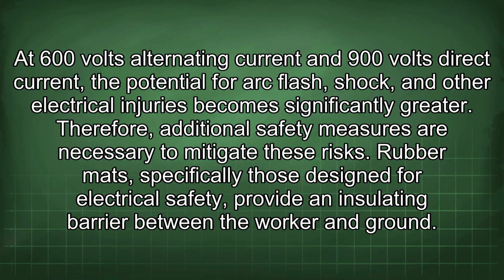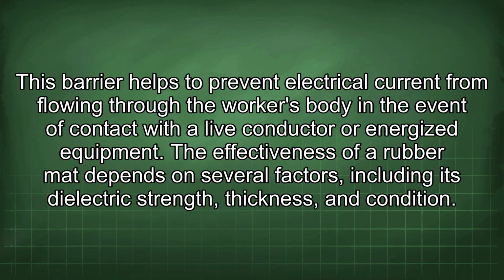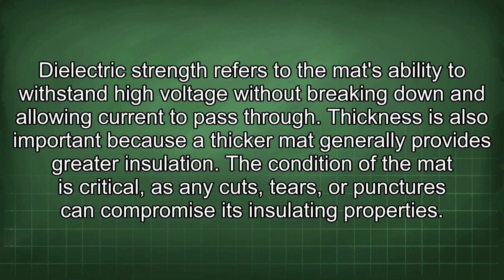Rubber mats, specifically those designed for electrical safety, provide an insulating barrier between the worker and ground. This barrier helps to prevent electrical current from flowing through the worker's body in the event of contact with a live conductor or energized equipment. The effectiveness of a rubber mat depends on several factors, including its dielectric strength, thickness, and condition. Dielectric strength refers to the mat's ability to withstand high voltage without breaking down and allowing current to pass through.